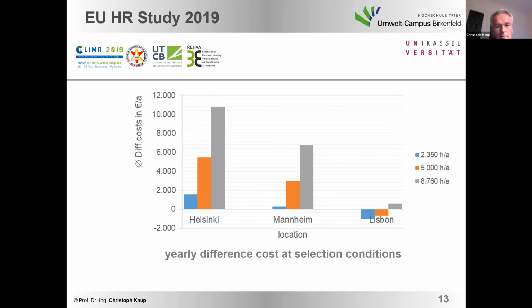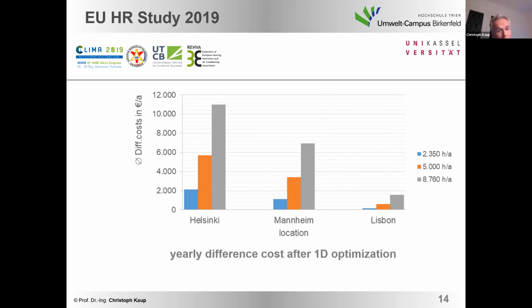But if you look to the southern parts, to Lisbon, for example, you see that with the status quo selections, the heat recovery systems which were used in these cases, we produce losses, especially if we have low operating times. After 1D optimization, compared to the status quo, we had the possibility to change the losses into winnings. Especially after 3D optimization, we have the possibility to increase the benefits to the maximum. But you see there is still a slope between the northern and the southern areas, and there is still the influence of the operating time, but not so hard and not so terrible as with the status quo selection.